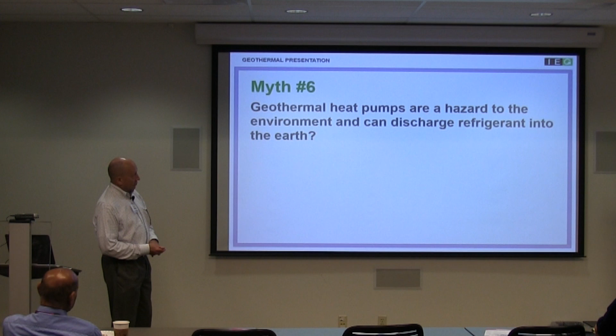In our experience over the years, we simply circulate tap water, or in some climates where we need a little bit of glycol, we'll use a food grade glycol, which is benign to the environment. Should it escape? Over doing this 20-some odd years, I've only had two occurrences of failures in loops at the bottom, at the U-bend, and it was a manufacturing defect by the same manufacturer — a global issue with that manufacturer.